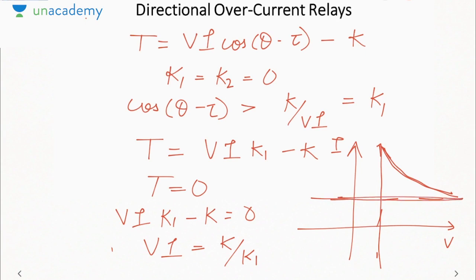So the thing to be remembered about the directional overcurrent relay is that it has one directional unit and one overcurrent unit. How does a directional overcurrent relay operate? It operates based on interaction of the fluxes produced by the fault current and the fault voltage. Now remember, this fault current and fault voltage are not the actual fault current and fault voltage. Rather, these are the stepped down values of fault current and fault voltage by means of the current transformer and potential transformer. So what I am saying is, the current transformer will step down the fault current for the relay operation.